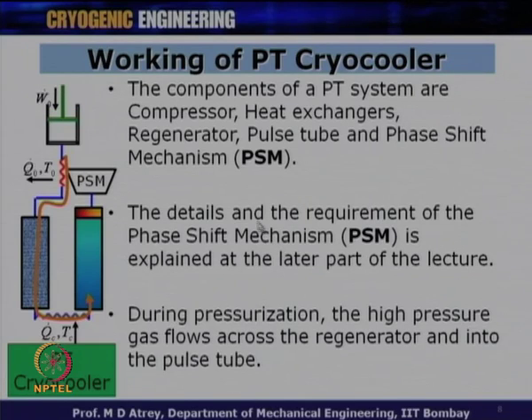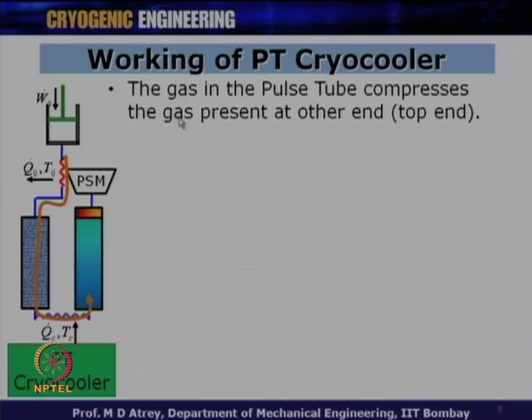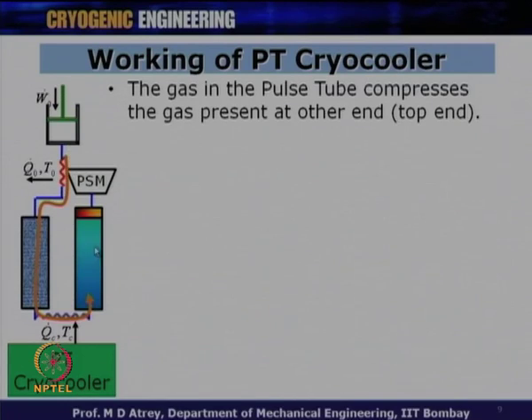How do we get cooling? The piston comes down and pressurization happens; the piston goes back and depressurization happens. During pressurization, high-pressure gas flows across the regenerator and into the pulse tube. The after cooler takes the heat of compression, the gas enters the regenerator, and then enters the pulse tube. The gas in the pulse tube compresses the gas present at the other end, which was initially at charging pressure. This compression results in a rise of temperature at the top end.